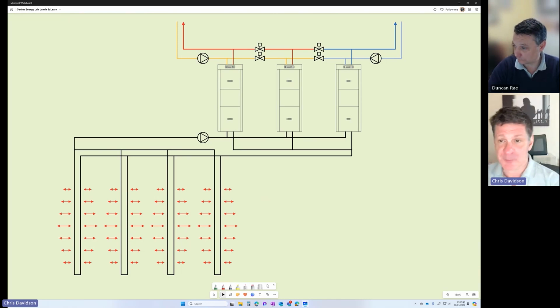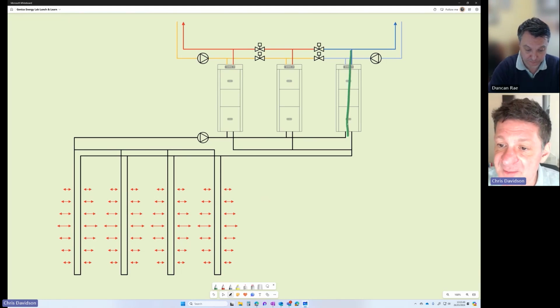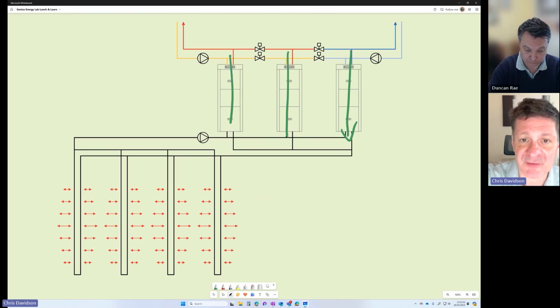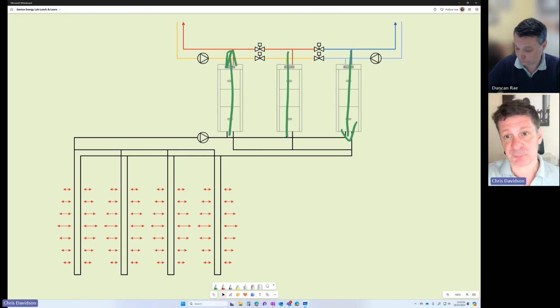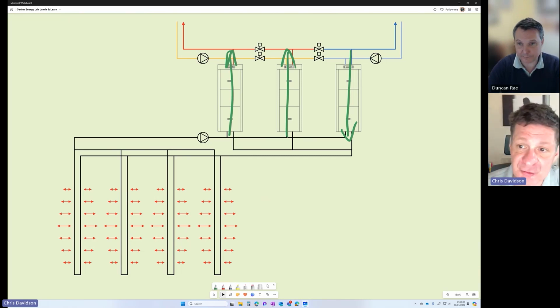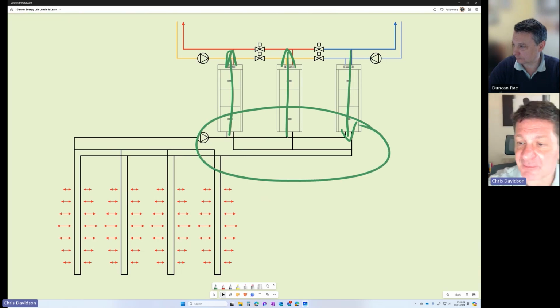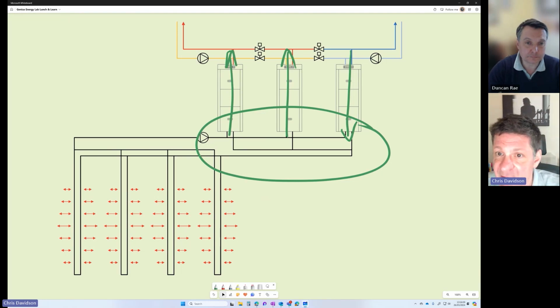What I've got here is a typical heating and cooling system in a commercial building. So what I've got is one heat pump cooling, so that's putting heat into the ground loop, and I've got a couple of heat pumps here heating. They are taking heat back out of that ground loop again. So right away you can see we've got energy recovery going on inside that ground loop in that header. Now there are quite a number of heating and cooling systems that will give you that instantaneous heat recovery.